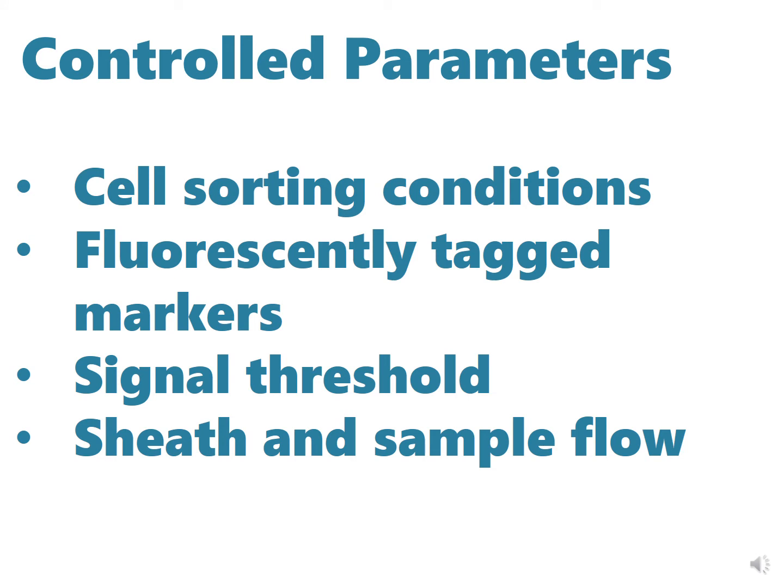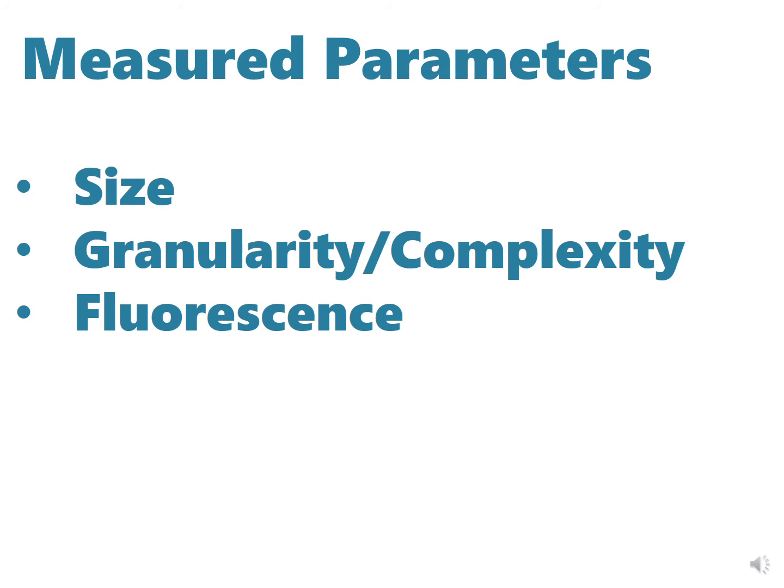Overall in this process, the user is able to control cell sorting conditions as well as fluorescent markers that are tagged. They can also determine the signal threshold as well as the sheath and sample flow. Measured intensity values will provide us with information on size and cell complexity. With the use of a fluorescent probe, we can increase the amount of parameters that's available to include certain cell populations or certain types of receptors that are on a cell.